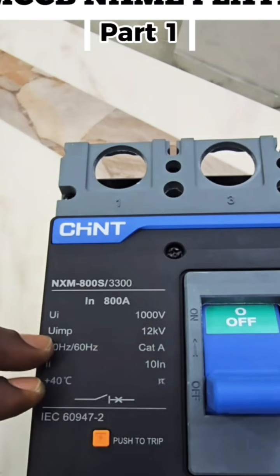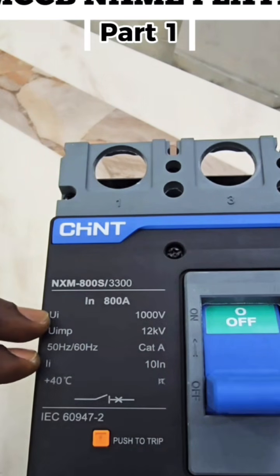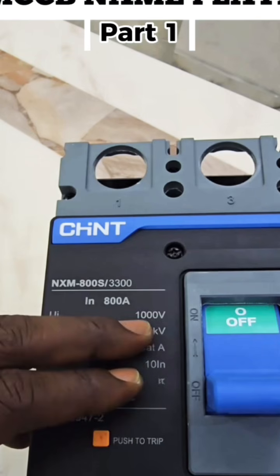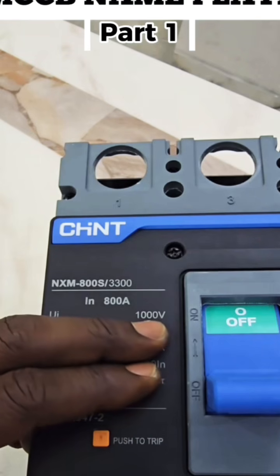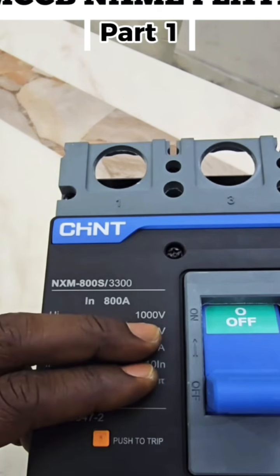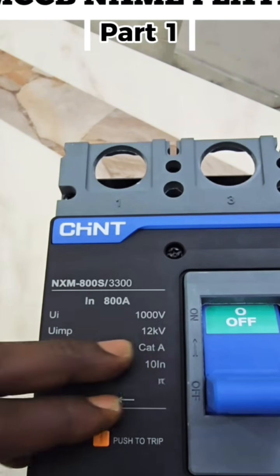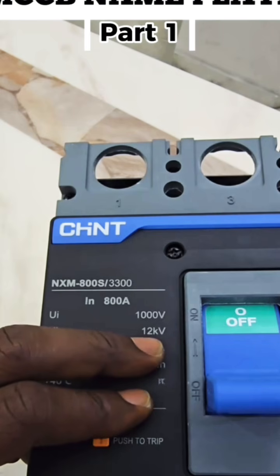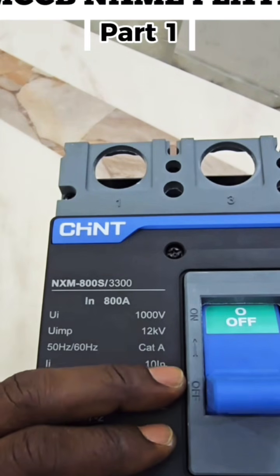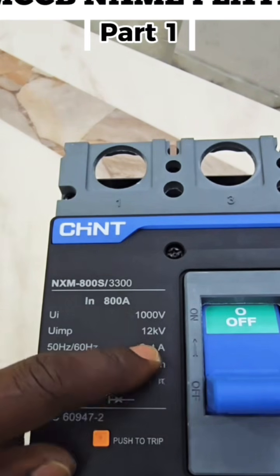The difference between UIMP and UI is that UI has to do with the maximum voltage the insulation can handle over a period of time, while UIMP is the maximum surge voltage this device can handle over a very short time without damage.